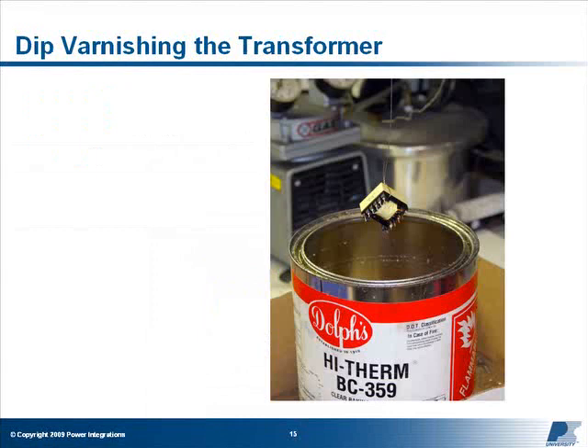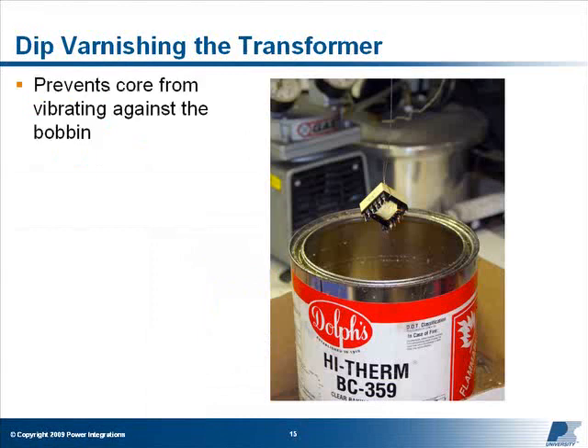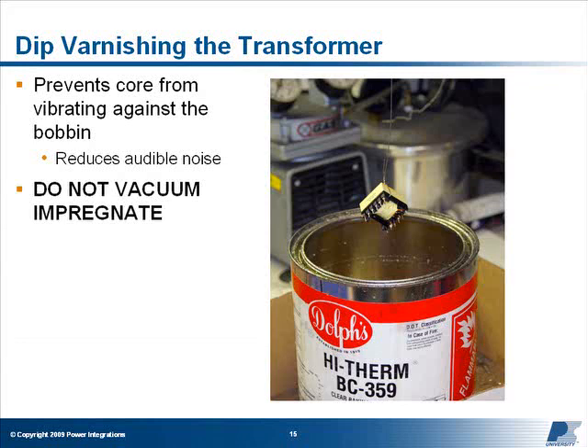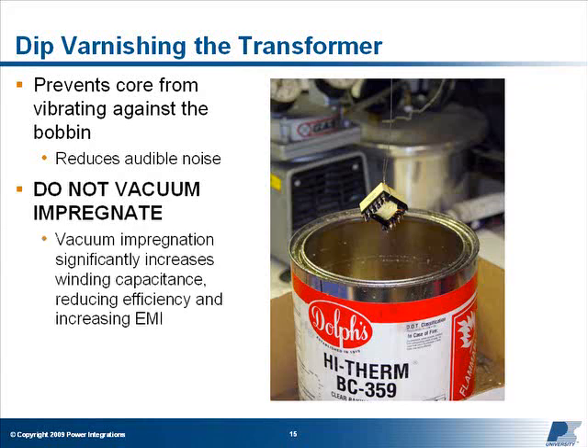Dip varnishing a transformer core will prevent the core from vibrating against the bobbin and will reduce audible noise. When specifying a varnishing technique with your vendor, always use dip and do not vacuum impregnate. Vacuum impregnation significantly increases winding capacitance and will reduce efficiency and increase EMI.